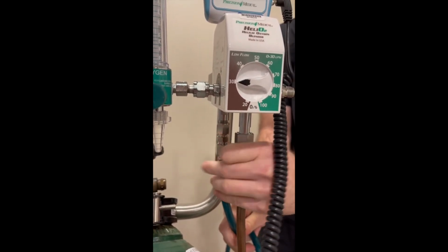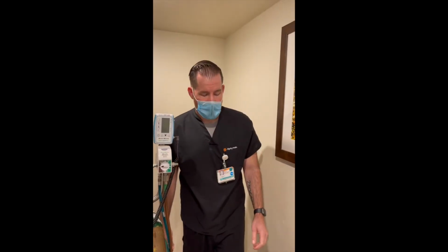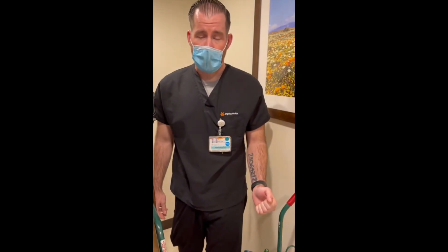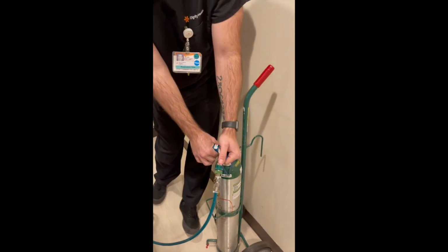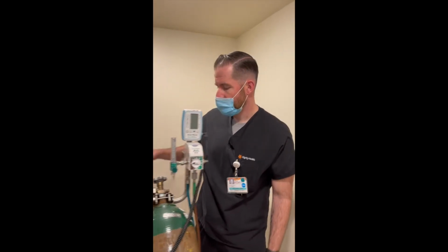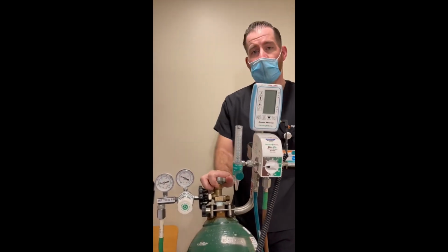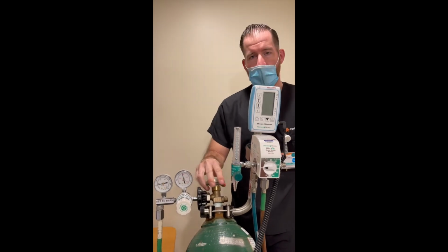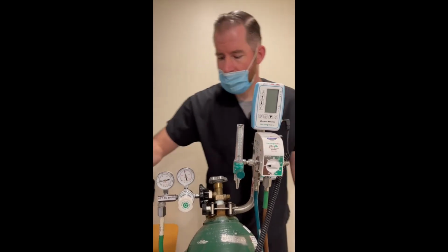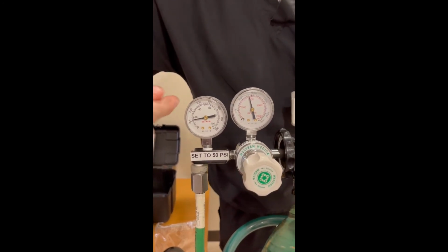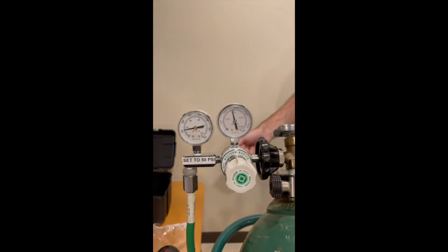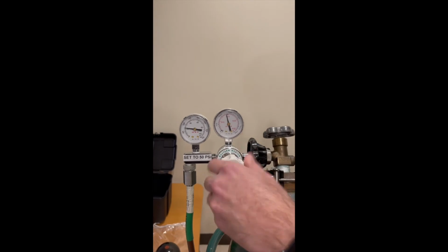Now we're going to simulate plugging the O2 into the 50 PSI quick connect. You'll immediately hear an alarm like this. Go to your H cylinder, crack the tank. Your alarm will persist. You'll have to ensure that your PSI is set to 50 in order for the alarm to go away. At 50 PSI, the alarm goes away.